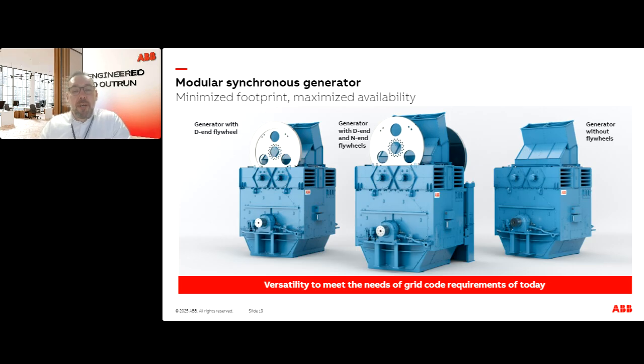Then lastly, like I already mentioned, the footprint is optimized due to the enhanced cooling, and due to the modular construction, the availability is maximized, because we have ready-designed flywheels and different frame constructions. Here you can also see a bit better where the flywheels are installed: here on the drive end of the machine, and then there's the possibility to have another flywheel on the non-drive end of the generator. This basically gives the versatility to meet the needs of grid code requirements of today and also tomorrow.